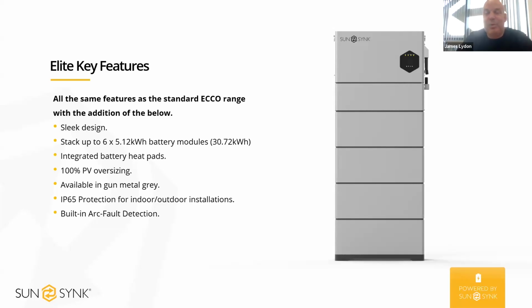You can see in the image here, we've got our inverter on the top. Just underneath the inverter, you've got what we call the power distribution unit, and that is essentially the isolation in between the batteries and the inverter. That has a 250 amp DC MCB built in. And then below that, we've got four batteries.